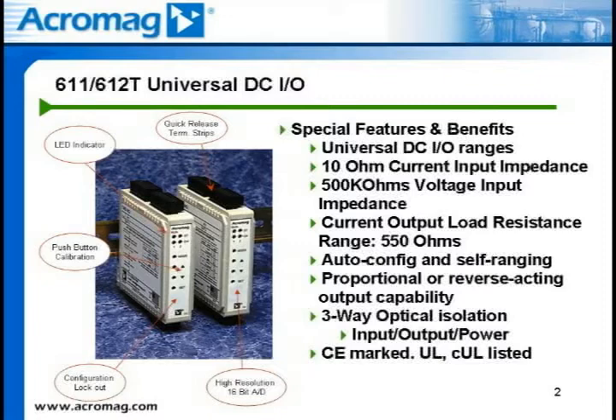The high voltage input impedance of 500 kiloohms offers the ability to do the same thing with wiring a circuit in parallel with minimum voltage or current loss. The output of the 611T and 612T isolated transmitter drives purely resistive loads. The current output load resistance range can be up to 550 ohms, or simply two 250 ohm load devices.